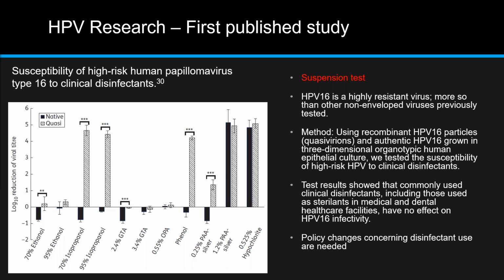previously tested. The method we use, we tested the surrogate or the recombinant HPV particles, the quasi-virions, versus the authentic HPV-16 grown in three-dimensional organotypic human epithelial culture. We tested the susceptibility of high-risk HPV to clinical disinfectants. The test results showed that the commonly used clinical disinfectants, including those used as sterilants in medical and dental healthcare facilities, had no effect on HPV-16 infectivity. So this made us state that policy changes concerning disinfectant use are needed. Next slide, please.